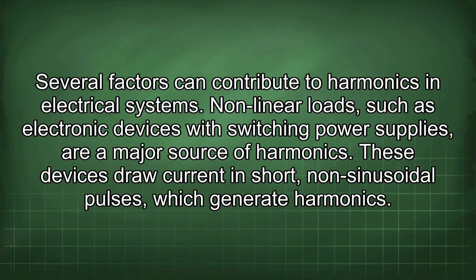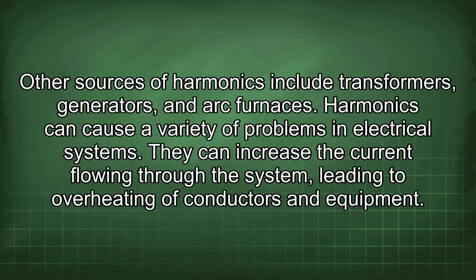Several factors can contribute to harmonics in electrical systems. Nonlinear loads, such as electronic devices with switching power supplies, are a major source of harmonics. These devices draw current in short, non-sinusoidal pulses, which generate harmonics. Other sources of harmonics include transformers, generators, and arc furnaces.